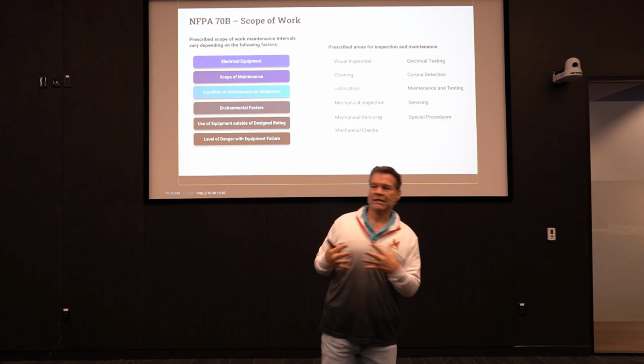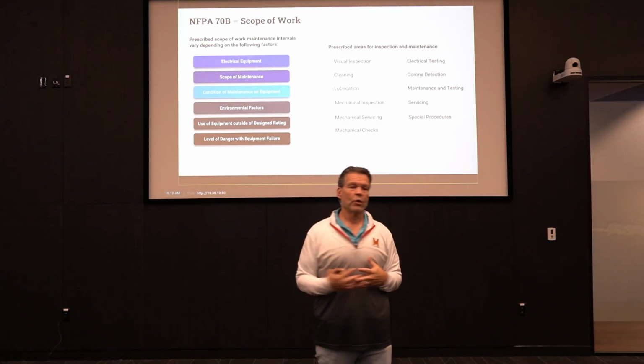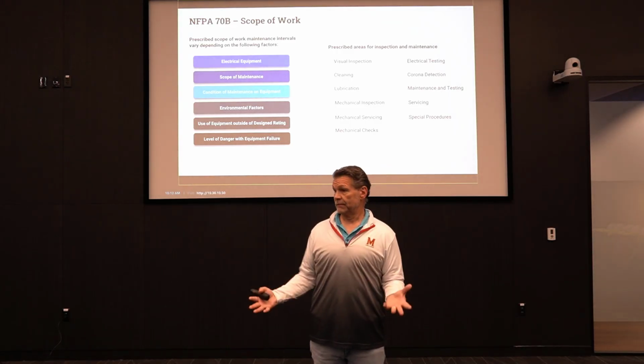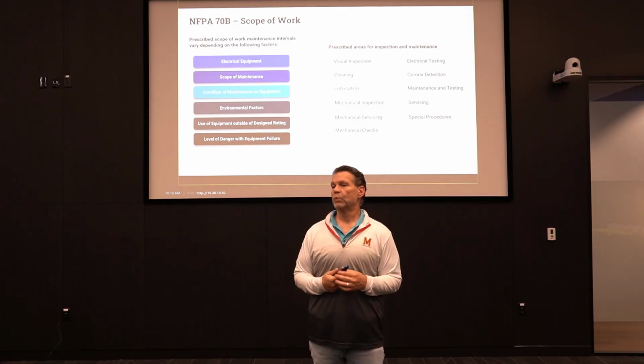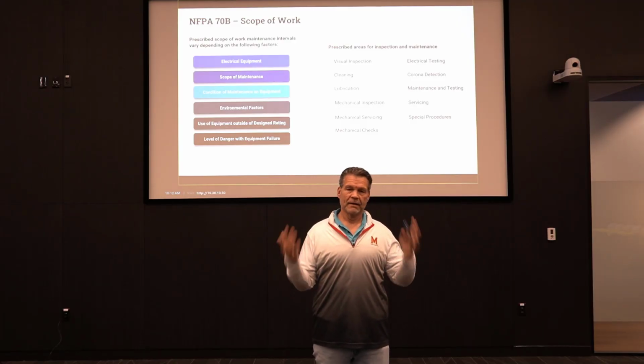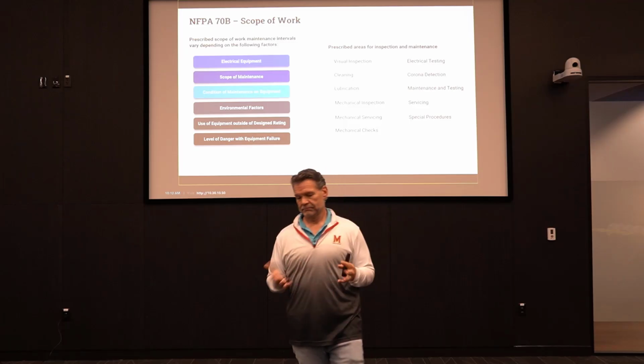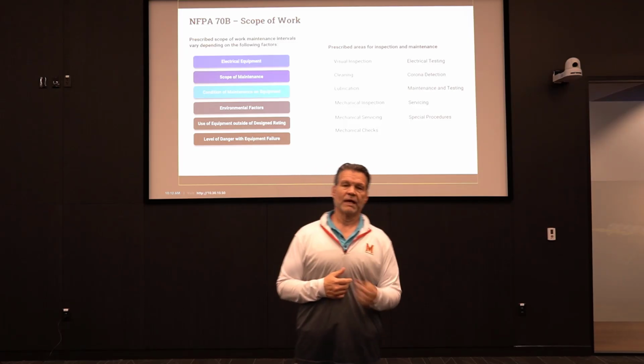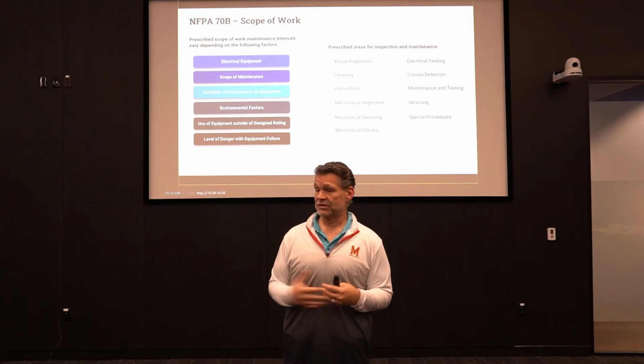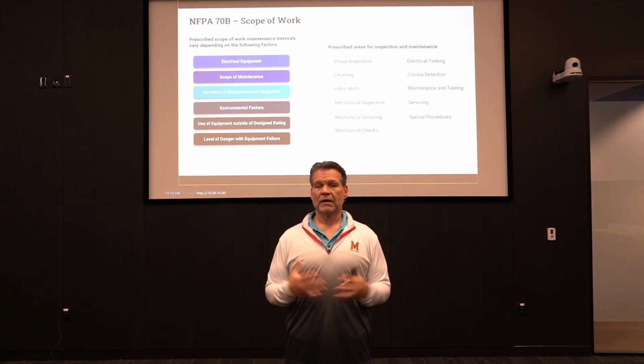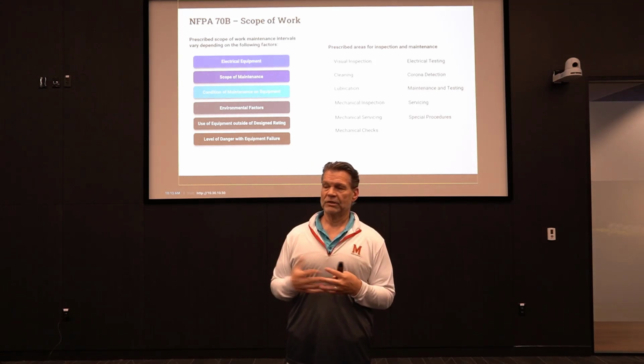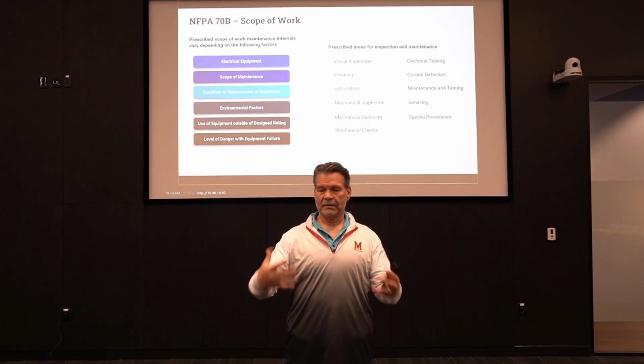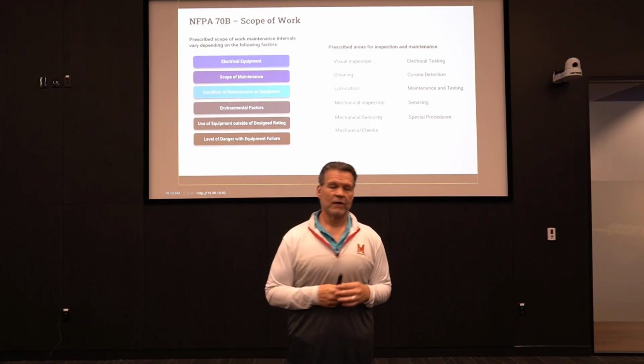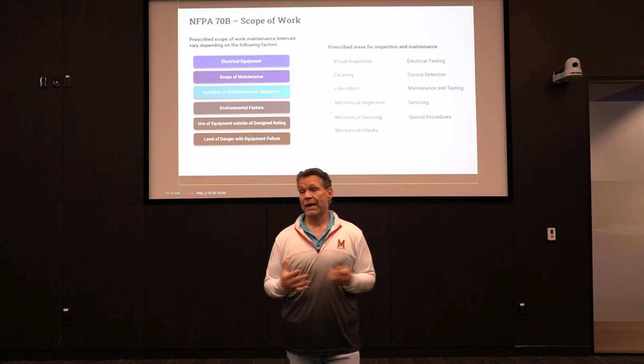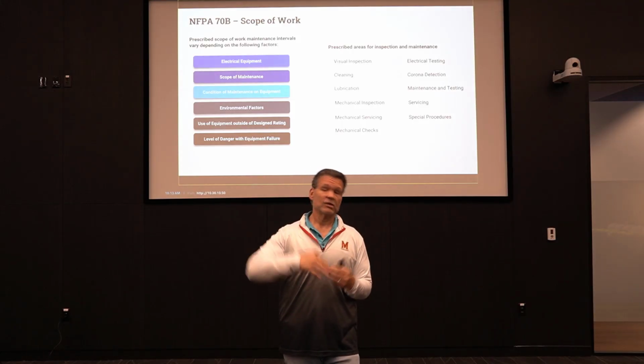So why is NFPA 70B important when it comes to safety? That's a very simple one to talk about. Let's say that we look at an arc flash label, and the arc flash label has the incident energy listed. The engineer has put in a calculation to decide on that arc flash label what the incident energy is. A lot of that depends on maintenance. It is clearing times.